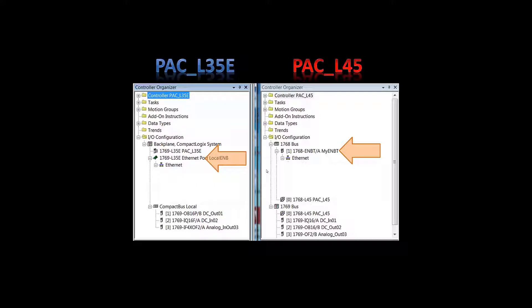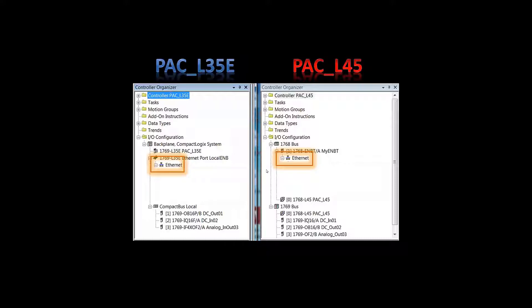The 1769 bus of the L45 and the Compact Bus Local for the L35E are identical. In addition, the L45 has the 1768 bus, to which you can add up to four 1768 modules — motion modules or communication modules, specifically Sercos fiber optic ring interfaces. Both controllers have Ethernet interfaces, one built-in and one added, giving us a method to connect the PAC-L35E and PAC-L45 together so they can communicate with each other.